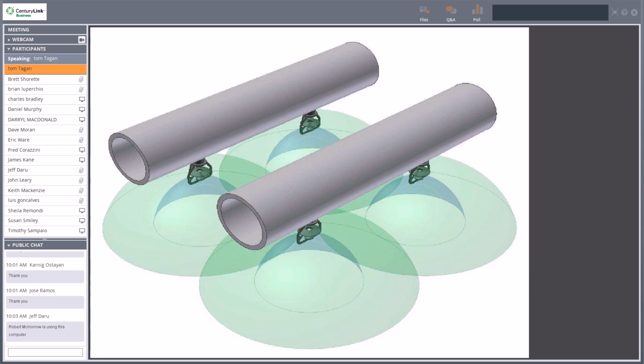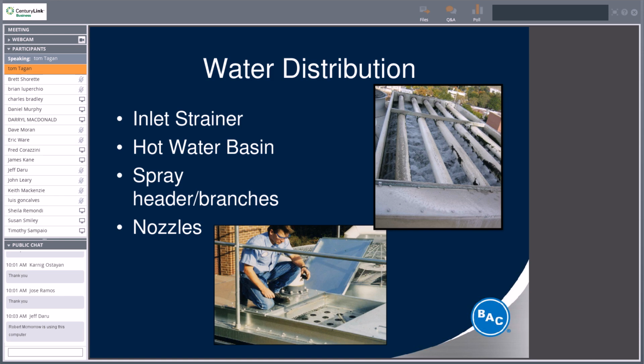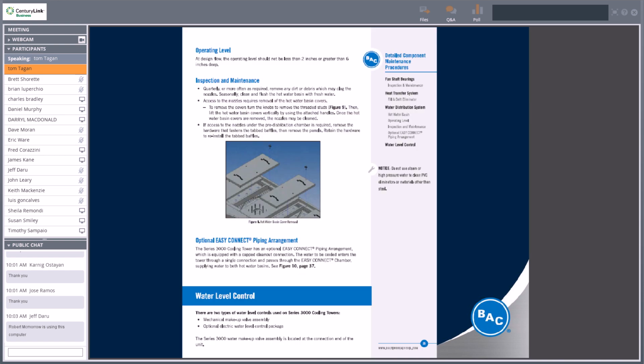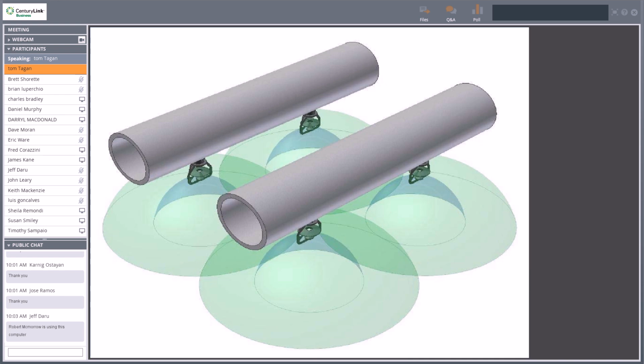This is just an engineer's rendering of the distribution pattern in one of those spray headers in the nozzles. As you can see, the water comes out, hits these deflector plates, and mechanically spreads over the fill. If we jump back a page, if you were to pull your drift eliminators off of this tower and see uneven water flow, that would indicate that some of these nozzles are clogged and need to be removed. In this case, you would have to unscrew the nozzle from here, clean it out if you can't clean it out in place.